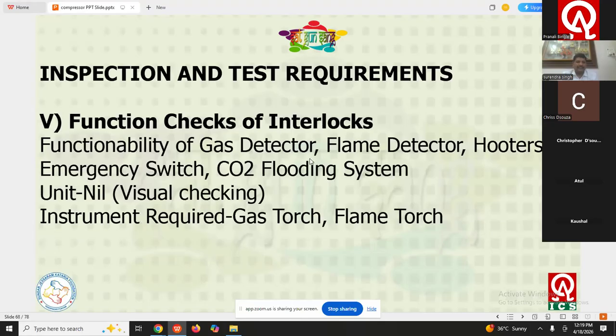Function checks of interlocks can check the gas detector, flame detector, hooters, emergency switch, CO2 flooding system. So they are the visual checking. No unit is required, no equipment is required. Only you have to check that the tripping system is there if any parameter is going beyond the limit. So you just check that the compressor is tripped or not at the required level.